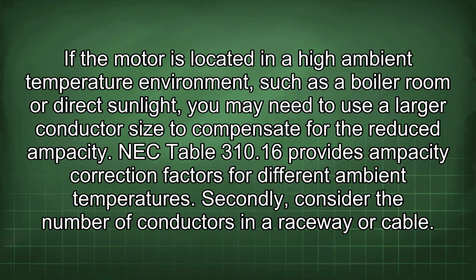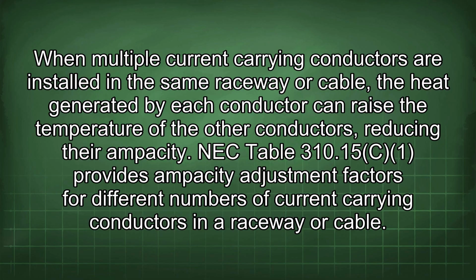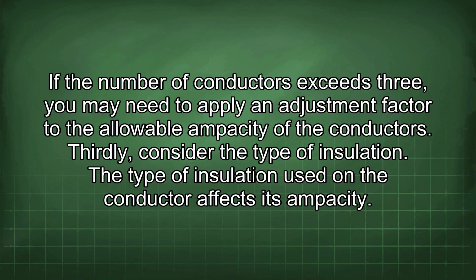Secondly, consider the number of conductors in a raceway or cable. When multiple current-carrying conductors are installed in the same raceway or cable, the heat generated by each conductor can raise the temperature of the other conductors, reducing their ampacity. NEC Table 310.15 provides ampacity adjustment factors for different numbers of current-carrying conductors in a raceway or cable. If the number of conductors exceeds 3, you may need to apply an adjustment factor to the allowable ampacity of the conductors. Thirdly, consider the type of insulation.